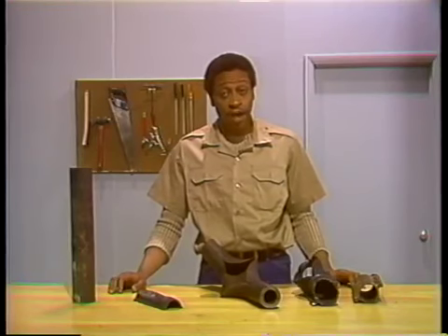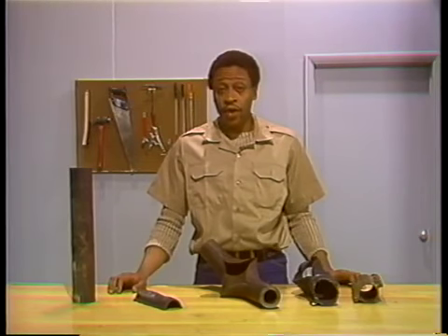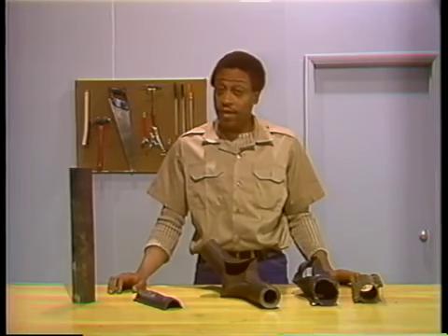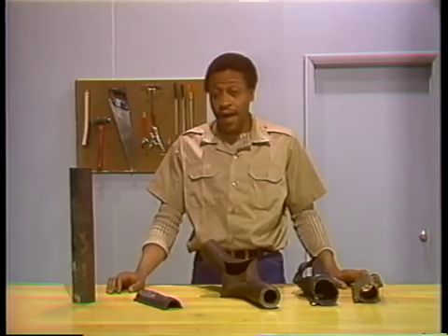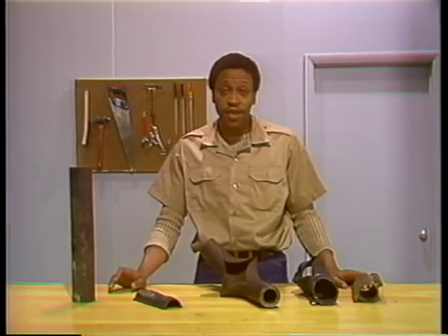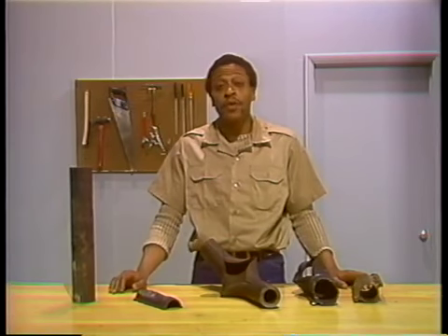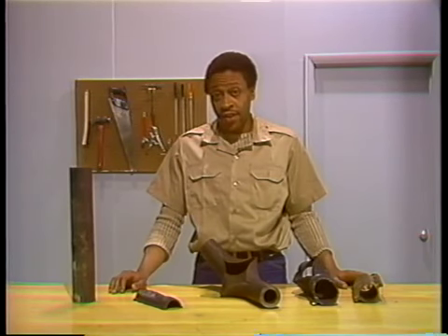Now that we've talked about tube failures, let's take a look at some tube deformities. Deformities, as we said earlier, are irregularities in the tube metal that can lead to failure. The first two types of deformities we'll look at are tube enlargement and heat blisters. Both of these are caused by overheating. Tube enlargement is common in superheater tubes. It appears as a uniform enlargement of a portion of the tube. The overheating that causes it is milder than the temperatures responsible for ruptures and cracking. But if an enlarged tube stays in service, it will eventually rupture or crack.